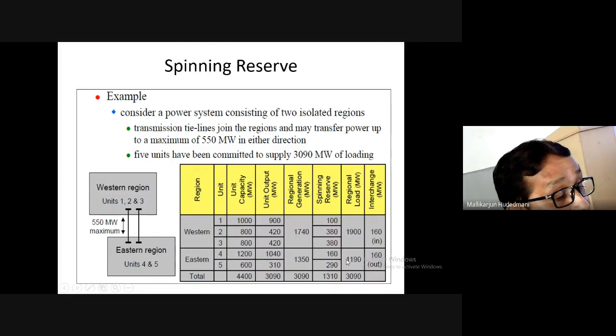That is the reason this spare energy in this generation area can go out to area AR1. Then, meantime, I can see any 160 variation. Suppose it demands 200. Is it able to cope up? 300 megawatt. Is it able to cope up? That is to be checked again by its capacity. The spare capacity from the fourth machine is 160 megawatt. From the fifth machine is 290 megawatt. So I have here 450 megawatt excess energy from the eastern region it can deliver. Right now, 160 megawatt is being pumped to make it balanced. So this 160 megawatt, if I allow it to float, the current generation will borrow 160 megawatt and balance their load.